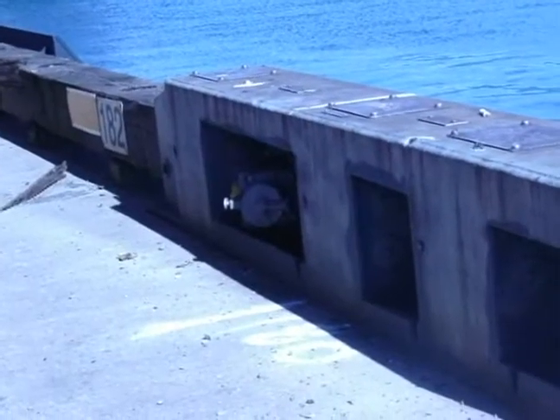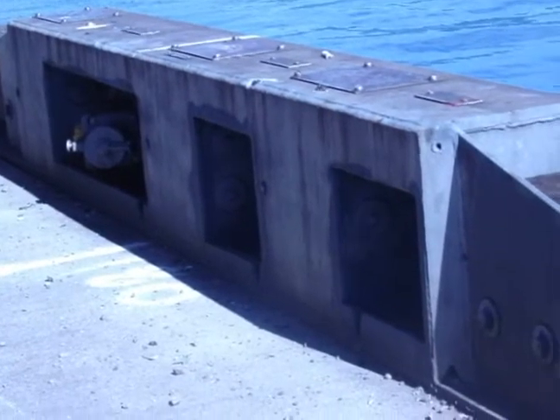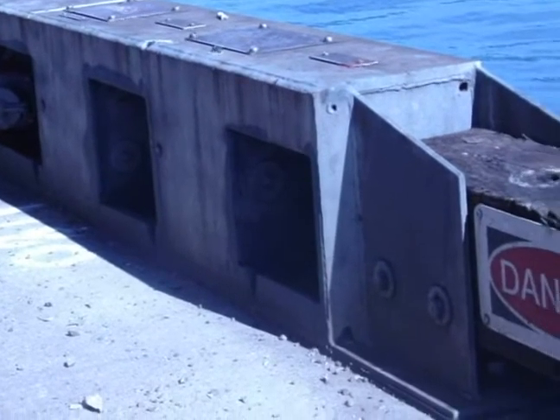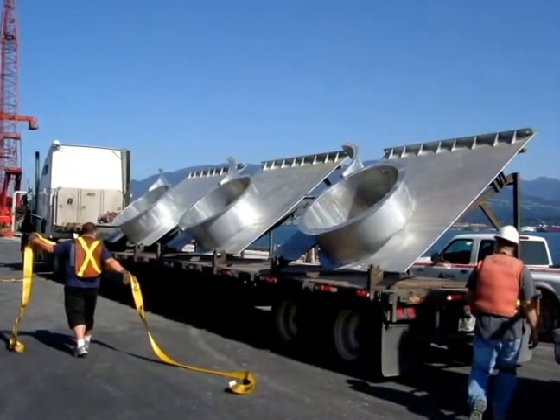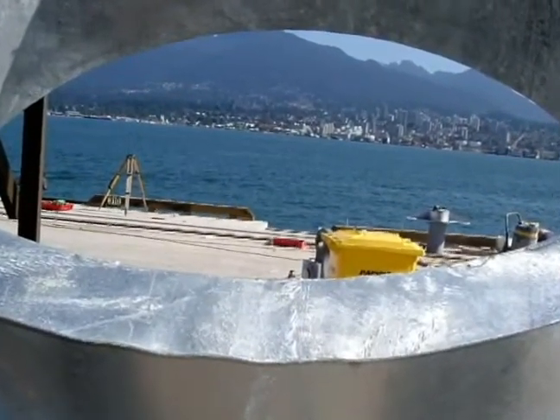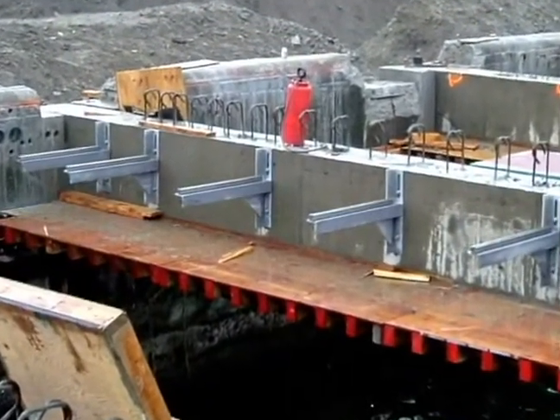The berth's bull rail boxes, which provide power to maintenance crews, were adjusted to withstand enormous force should the box come in contact with a ship or an anchor. The cable cassettes, which align and relieve tension from the crane's cable system, were also modified. These 10-foot galvanized structures were custom-ordered from the eastern United States. All conduit beneath the berth was made of fiberglass, and Houle custom-designed the brackets to hold the conduit as well as the expansion joints.